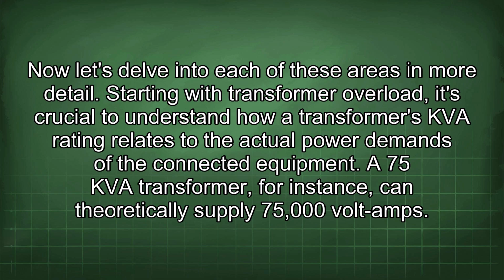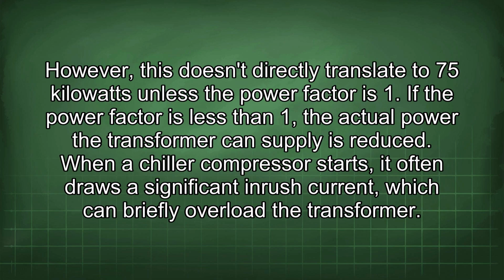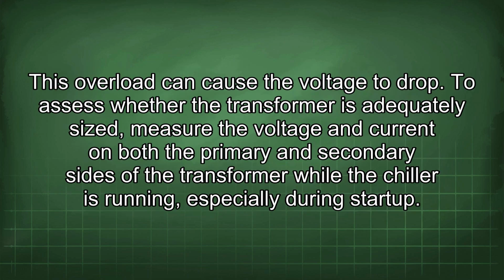Starting with transformer overload, it's crucial to understand how a transformer's kVA rating relates to the actual power demands of the connected equipment. A 75 kVA transformer, for instance, can theoretically supply 75,000 volt amps. However, this doesn't directly translate to 75 kilowatts unless the power factor is 1. If the power factor is less than 1, the actual power the transformer can supply is reduced. When a chiller compressor starts, it often draws a significant inrush current, which can briefly overload the transformer. This overload can cause the voltage to drop.